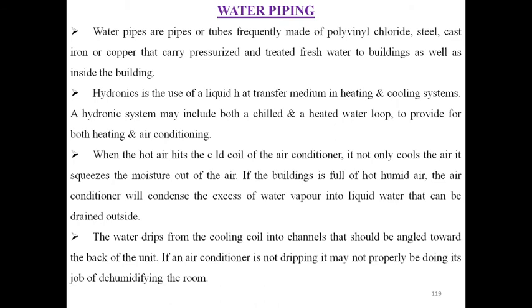If the building is full of hot humid air, the air conditioner will condense the excess water vapor into liquid water that can be drained outside. The water drips from the cooling coil into channels that should be angled toward the back of the unit. If the air conditioner is not dripping, it may not be properly dehumidifying the room.